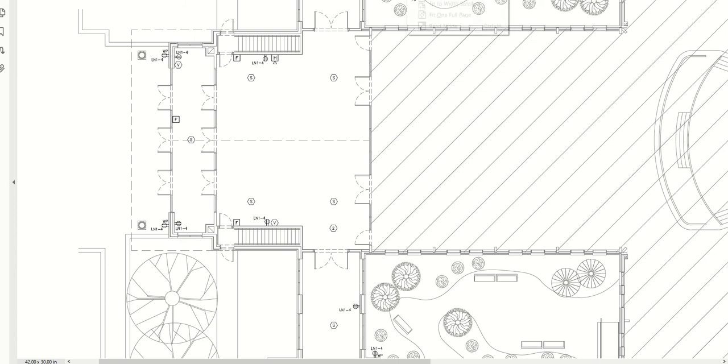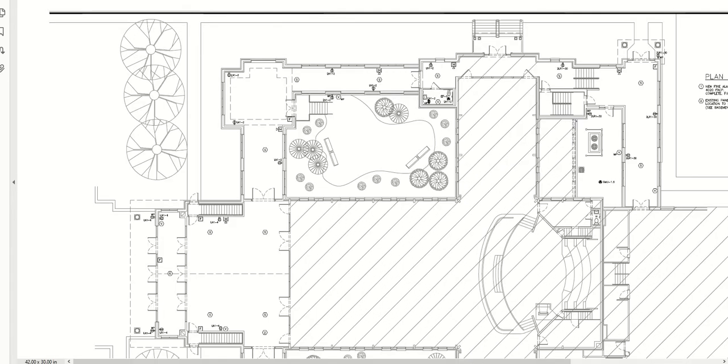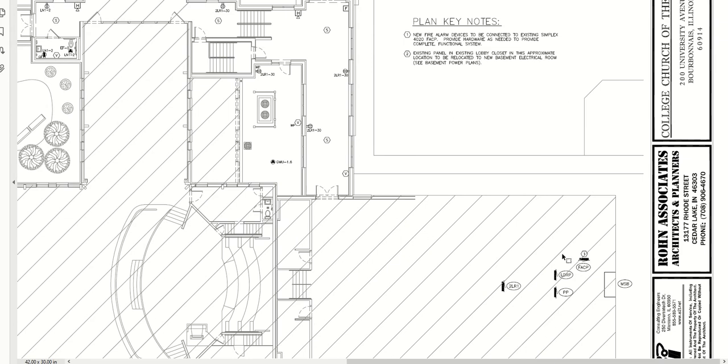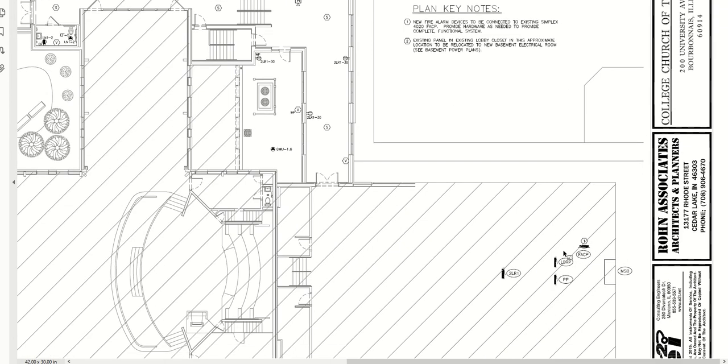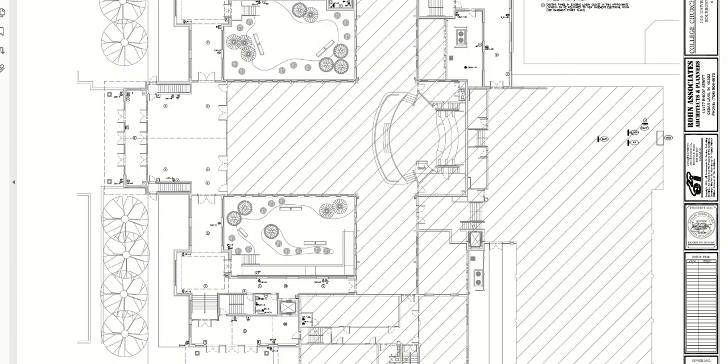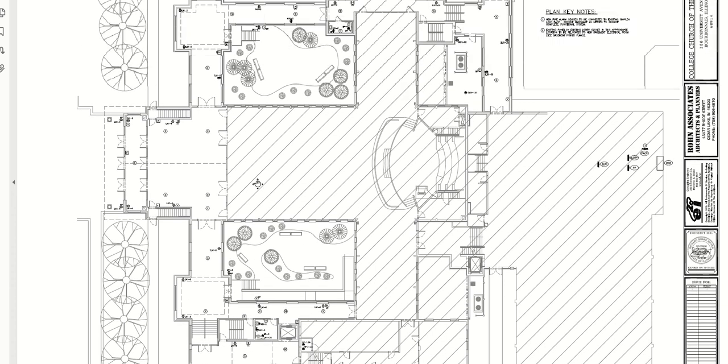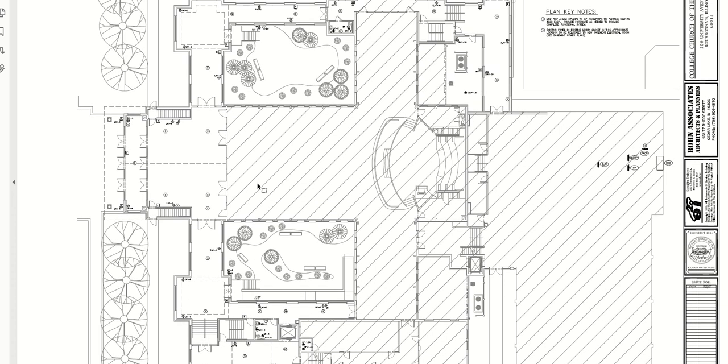We do show the existing panel locations. The main switchboard is back here and we have some panels back here that we utilized. For that reason, we need to show their location even if they're not doing new work in that area, because the electrical contractor needs to know where they are so he can figure how long his circuit runs or feeder runs will need to be. It's important to identify all the affected equipment in an existing project.